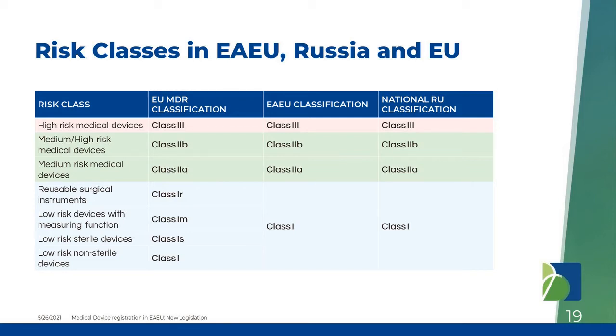The next important topic is risk classification in the Eurasian Union. Comparing MDR, Russian national classification, and Eurasian classification: the Eurasian Union risk classification uses the same classes. The European Union classification has a more detailed first risk class, while Eurasian Union classification has only one first risk class — there was an attempt to adopt the European approach to risk classification, but currently there is only one Class I.